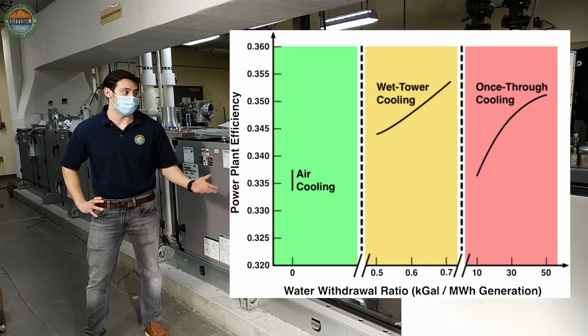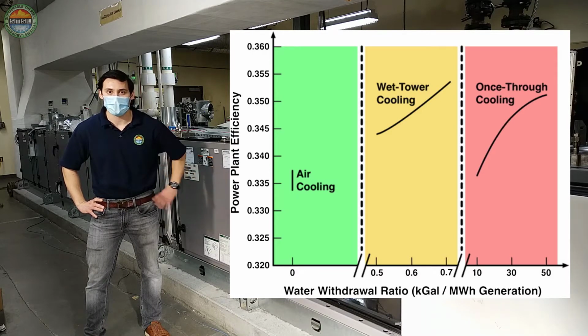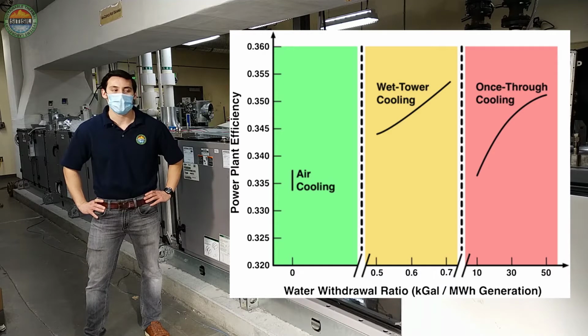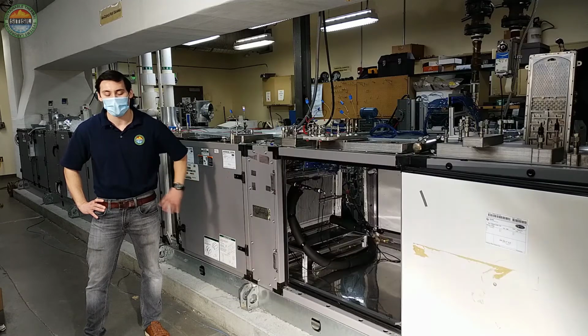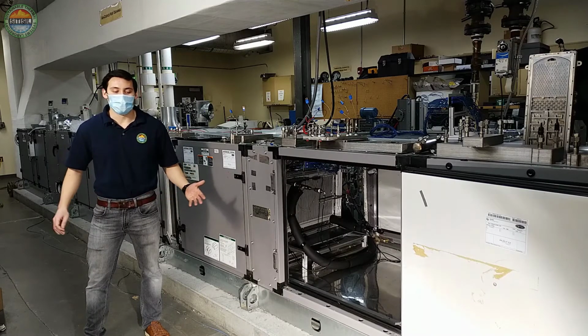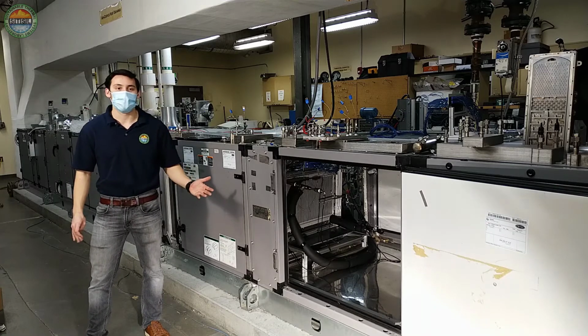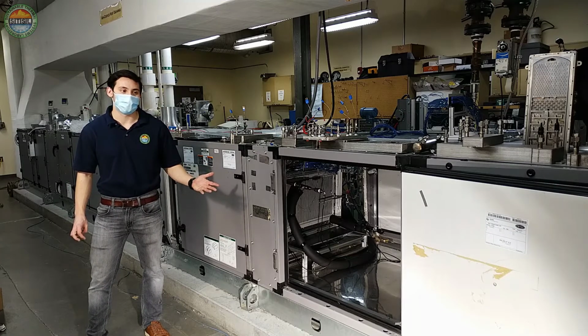To address this issue, we are investigating the use of air-cooled condensers specifically for power plant cooling. These air-cooled condensers greatly reduce water use, but they also decrease thermal power plant efficiency by about 5 to 10%. So we've been conducting experiments on airside enhancement methods, as well as thermal power plant optimization studies, to see how we could increase efficiency for a power plant using air-cooled condensers.